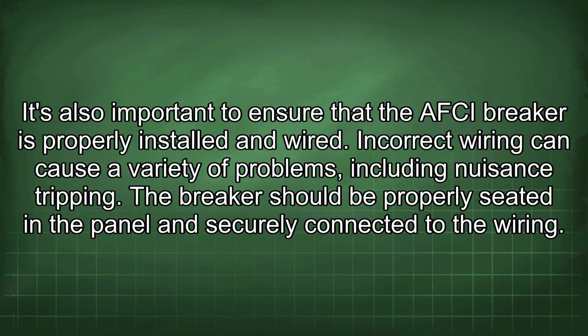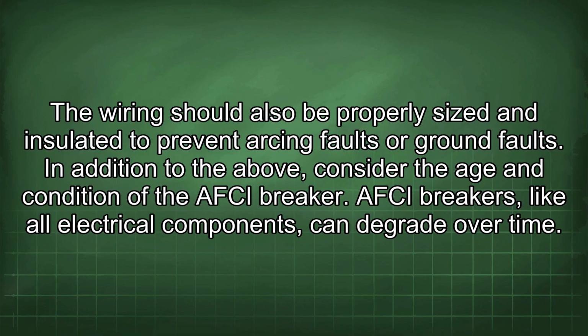It's also important to ensure that the AFCI breaker is properly installed and wired. Incorrect wiring can cause a variety of problems, including nuisance tripping. The breaker should be properly seated in a panel and securely connected to the wiring. The wiring should also be properly sized and insulated to prevent arcing faults or ground faults.